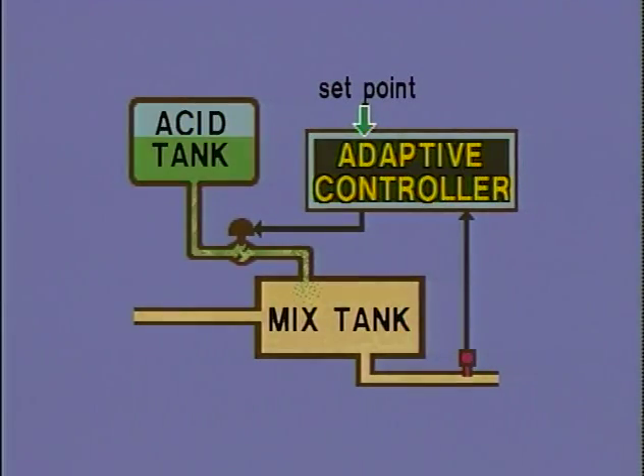Fortunately, there was a way to solve the pH problem. This was done by adding a feedback control loop to measure the pH of the product in the mix tank and make additional adjustments if required to bring the product to specification. The feedback loop included an adaptive controller to correct for non-linearities in the disturbance variable. An adaptive controller was used since pH response is non-linear, and an adaptive controller can automatically adjust its response to compensate for non-linearities in a system.